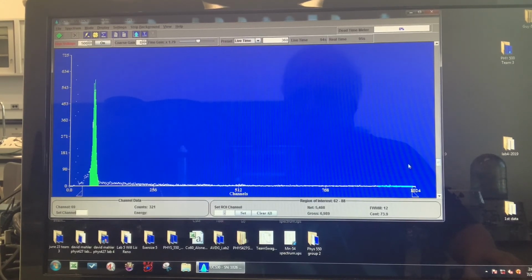Remember, the lower the R value, the better you are able to discriminate nearby gamma energies. So this is a poorer resolution. We go from 16% all the way to 4% with the highest energy gamma. So that summarizes this first lab. I think we've covered most of the basics.